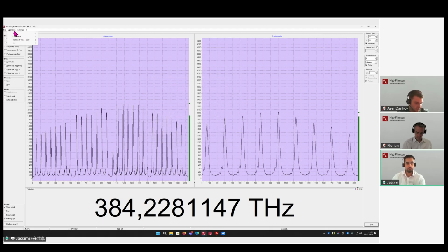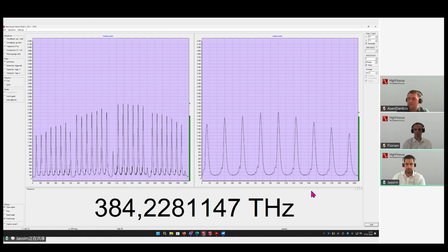For the calibration, this simply can be done in Operations, Calibrations, Wavelength Calibration. And here you have several options. You can choose a HeNe or another laser. In our case, we are actually using another laser. As I said, this is the rubidium-based calibration source that we have. And yeah, this is what you can do, and simply press OK to calibrate your wavelength meter.